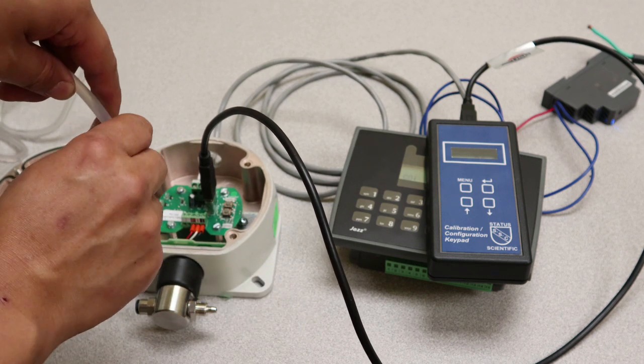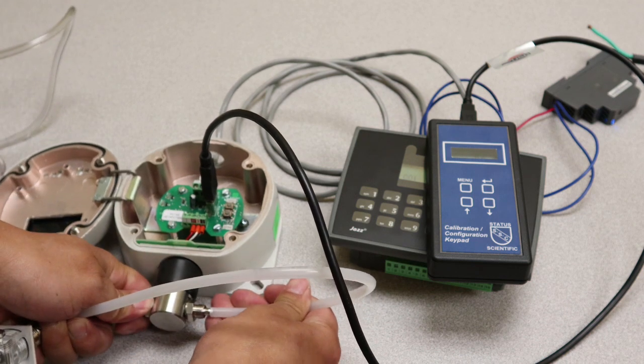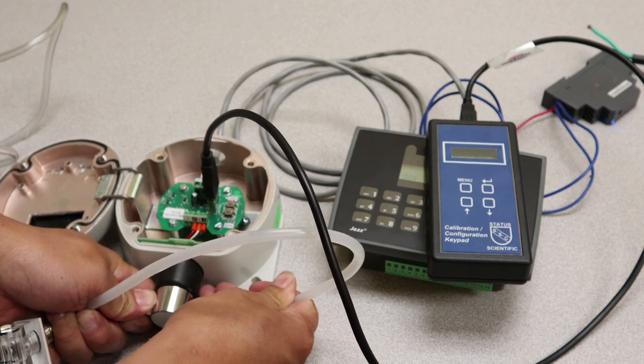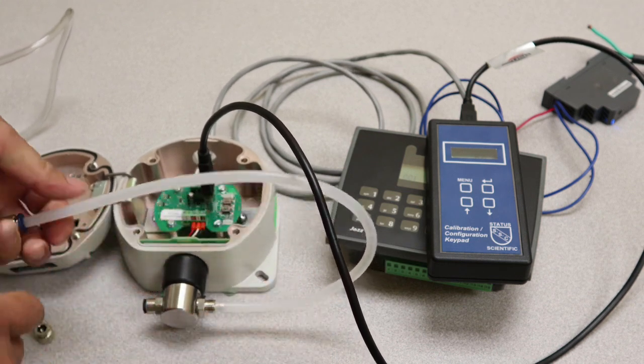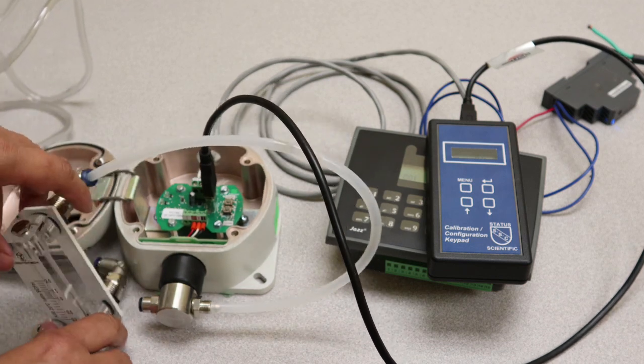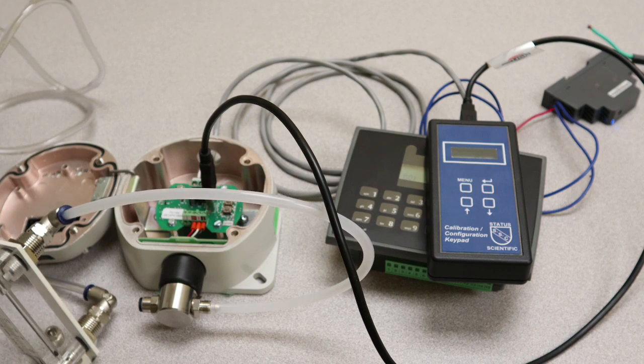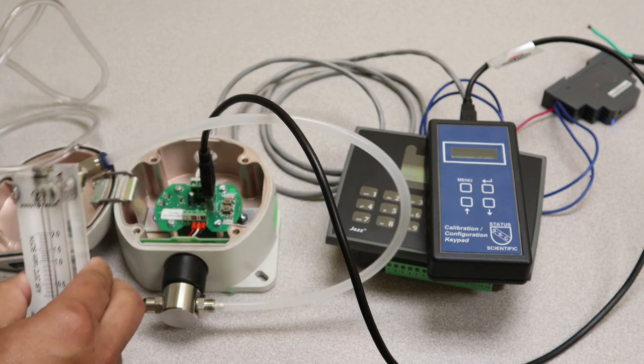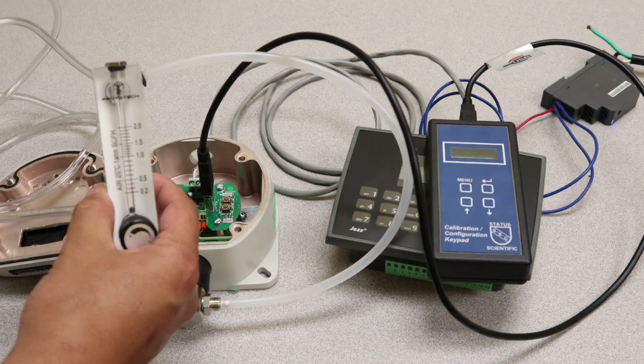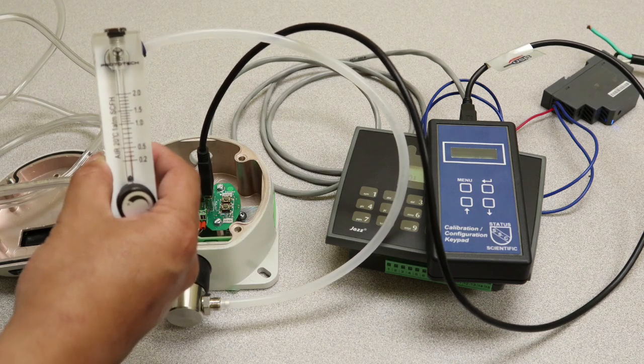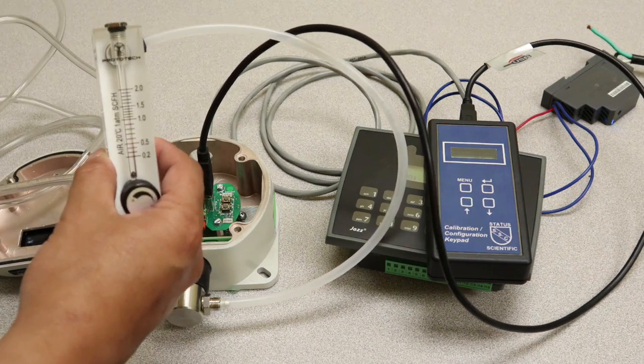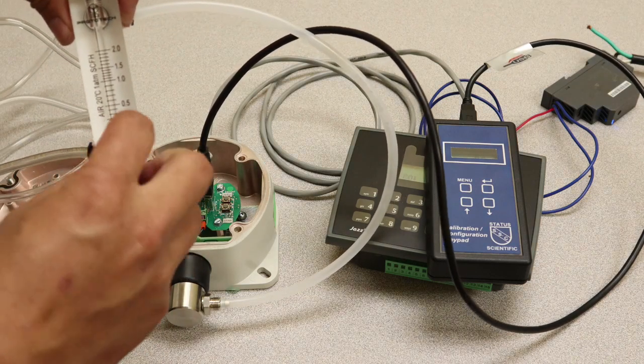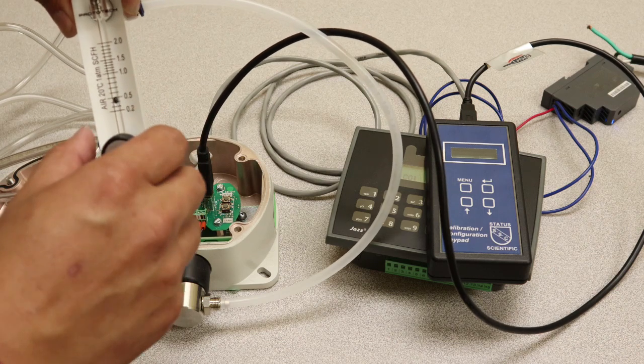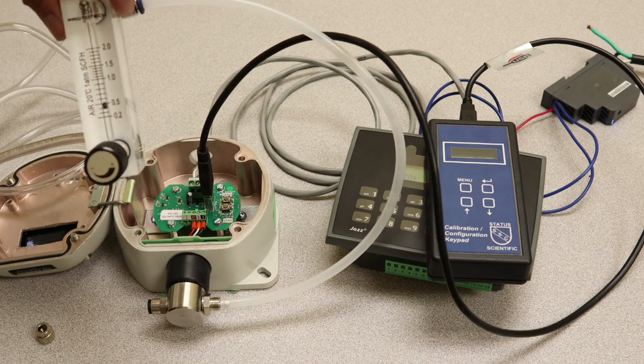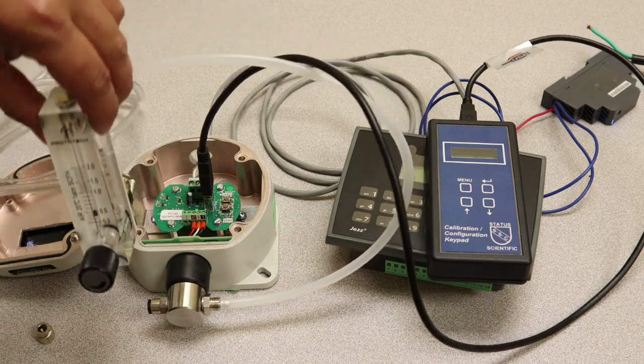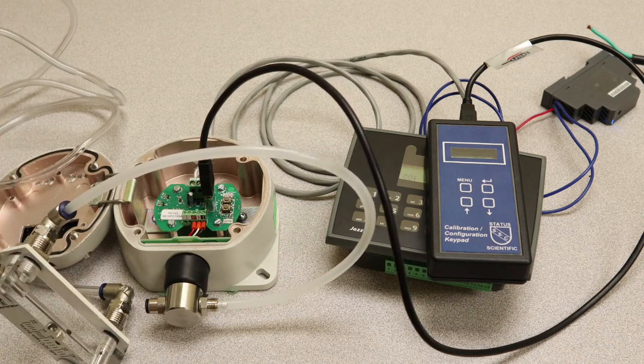What you can do in here is you can either connect it to the open port, which is this end right here, because the left side is normally reserved for the system, or you can disconnect it from the system and make the connection there. So once you have done that, we're going to feed it with some gas. We'll crack open the bottle. And as we crack open the bottle, we should see the CO flow meter start rising. You want to set it to about 0.5 SCFH. And then once you've done that, leave it connected for about 30 seconds to a minute.